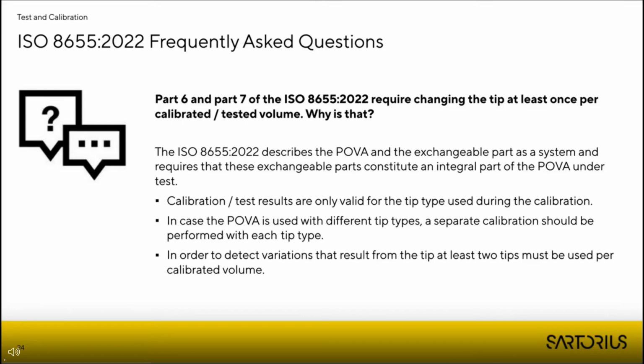But let's go on with 2 more frequently asked questions. Why do Part 6 and 7 of the new ISO require a tip change during the calibration? As explained earlier by Joni, the new ISO describes the pipette and the tip as one system, which means that the exchangeable parts are now seen as an integral part of the whole pipette. And therefore, calibration results are only valid for the tip type used during the calibration.